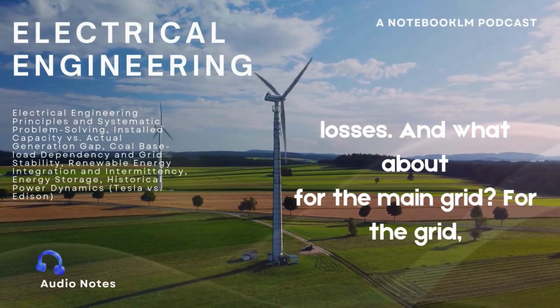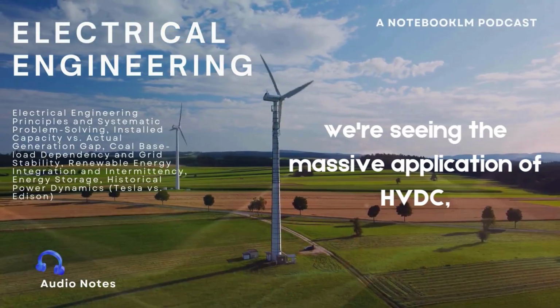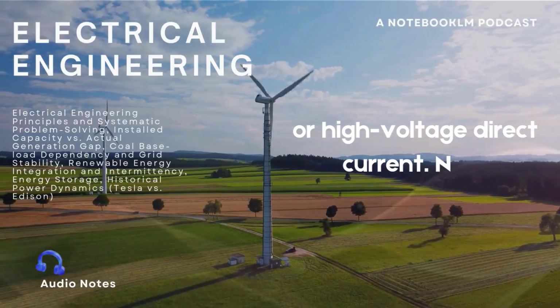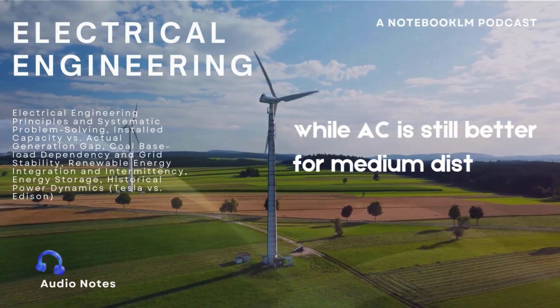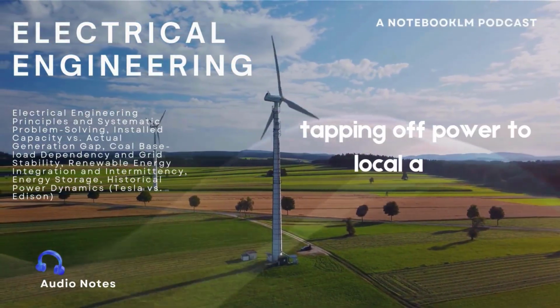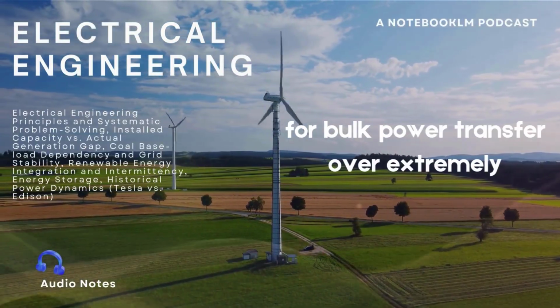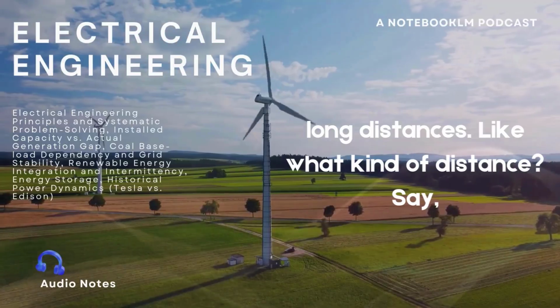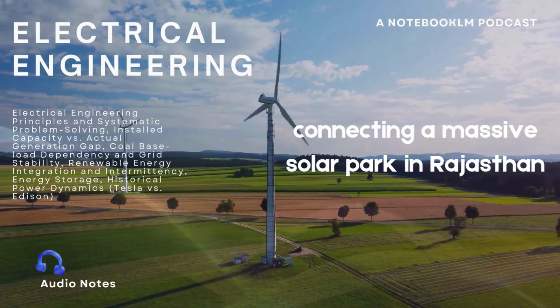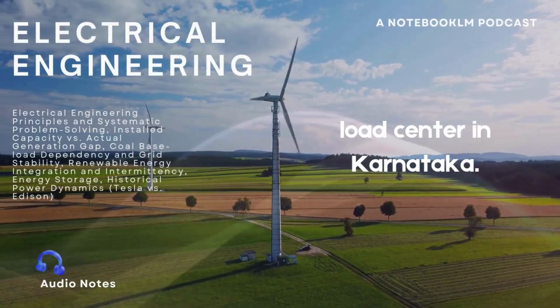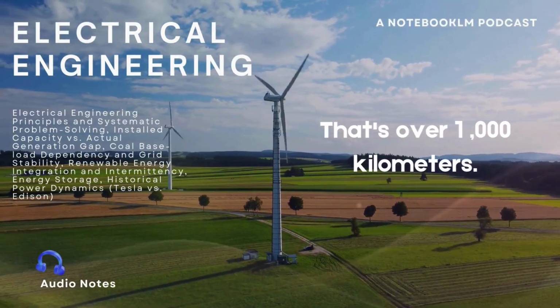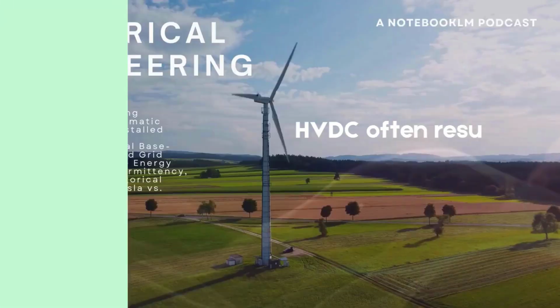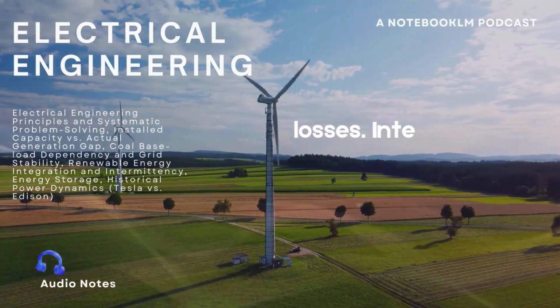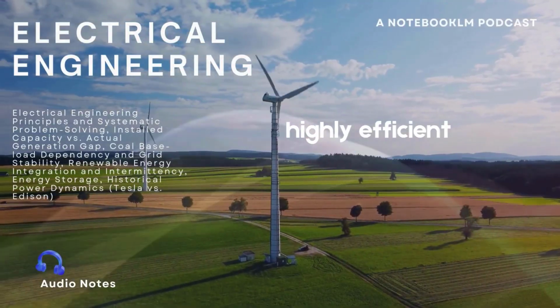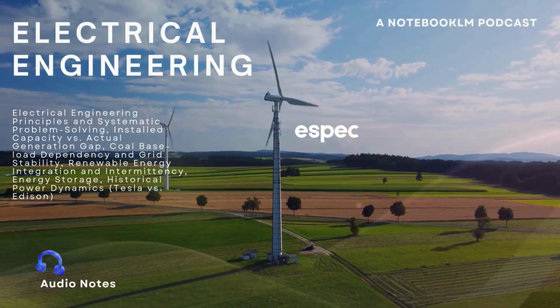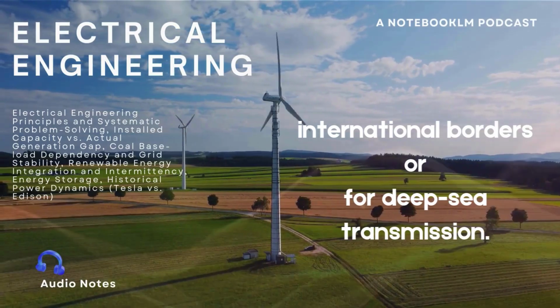And what about for the main grid itself? For the grid, we're seeing the massive application of HVDC, or high voltage direct current. Now, while AC is still better for medium distances and for tapping off power to local areas, for bulk power transfer over extremely long distances. Like what kind of distance? Say, connecting a massive solar park in Rajasthan to a load center in Karnataka. That's over 1,000 kilometers. Over that kind of distance, HVDC often results in lower overall losses. Interesting. It's a very targeted, highly efficient solution for bulk power transfer, especially across, say, international borders or for deep-sea transmission.